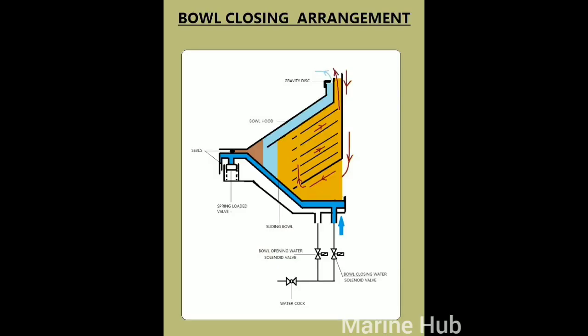Bowl closing operation: After the purifier reaches the rated speed, bowl closing water solenoid valve will open for a predetermined period. Once the water enters into the water chamber, the sliding bowl will move up and close the bowl with the bowl hood. There is a seal between bowl hood and sliding bowl.